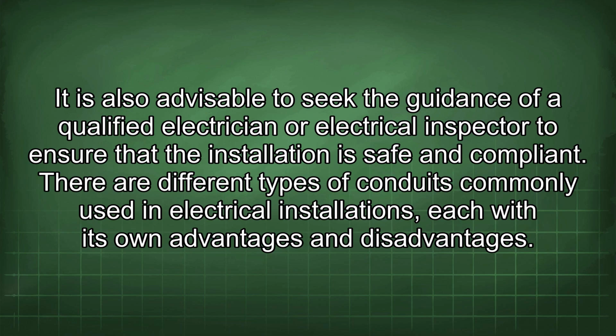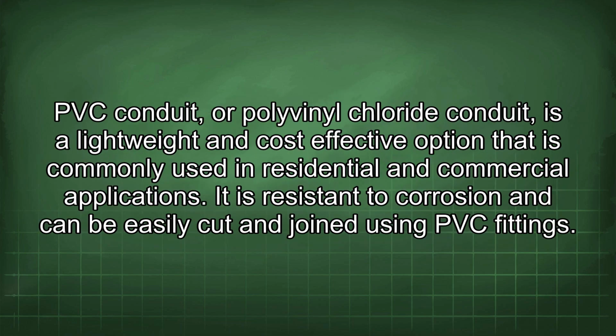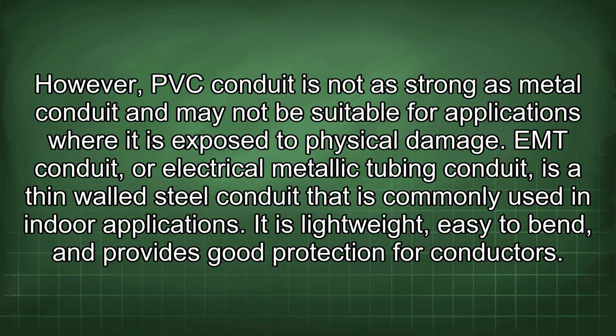There are different types of conduits commonly used in electrical installations, each with its own advantages and disadvantages. PVC conduit, or polyvinyl chloride conduit, is a lightweight and cost-effective option that is commonly used in residential and commercial applications. It is resistant to corrosion and can be easily cut and joined using PVC fittings. However, PVC conduit is not as strong as metal conduit and may not be suitable for applications where it is exposed to physical damage.